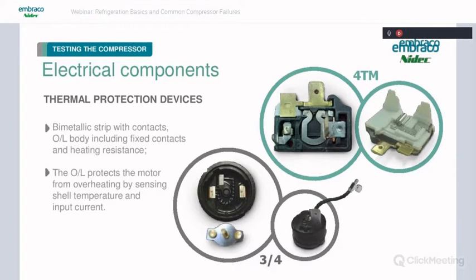They have a little heater wire underneath the contacts, which are mounted on a bimetal piece of metal here. And that heater, when you sense heavy current through that wire there, it's going to heat up. It's going to cause that bimetal to deflect and open the contacts. And given some time to cool off, it's going to snap back down, and it's going to close again. So it's a basic continuity check through these devices.